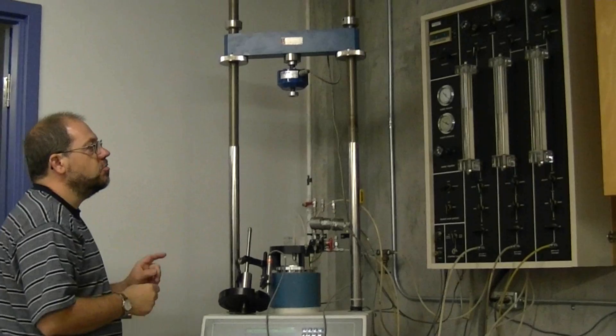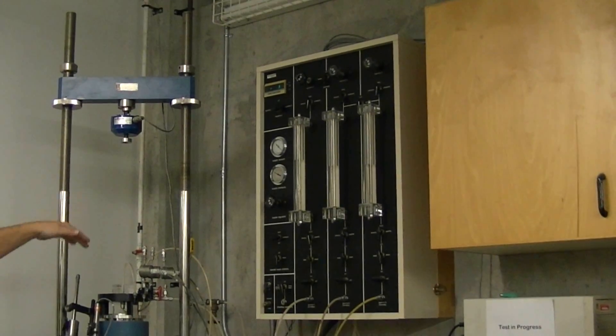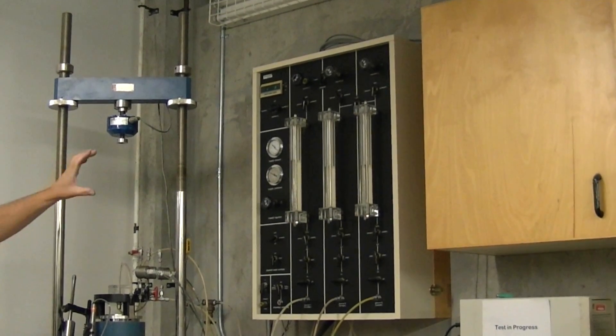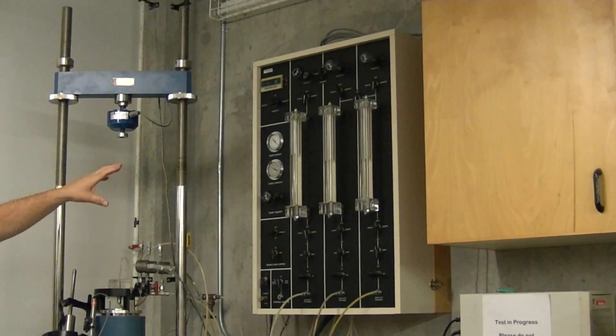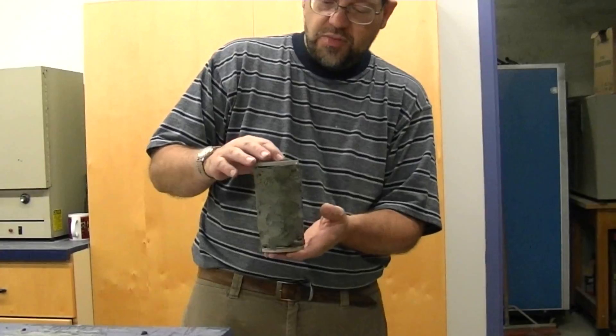The panel provides us with the ability to provide pressure to all three locations: the cell, the top and the bottom of the sample. We can also monitor the change of volume during the test by watching the water columns change.